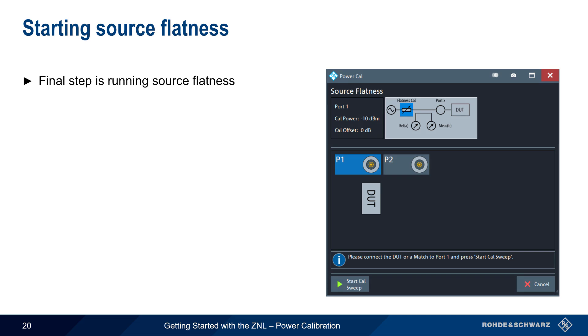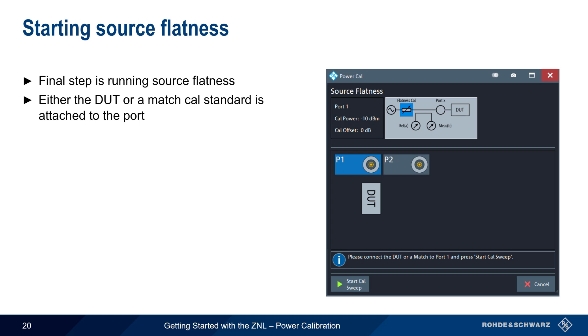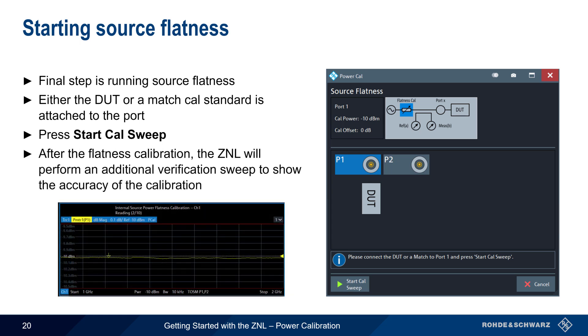The final step in power calibration is running source flatness. This can be done either by connecting the DUT to the port or by attaching a match calibration standard. As before, simply press Start Cal Sweep and follow the prompts. After the flatness calibration is completed, the ZNL will perform an additional verification sweep to show the accuracy of the overall calibration.